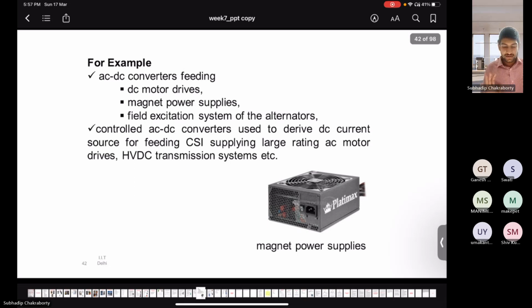My main point is this. I should understand my loads, the nature of my loads. Accordingly, I will select based on my cost and economic obligations. I will decide whether to go ahead with passive power filters and passive compensating elements, a low-cost arrangement for a more or less fixed kind of loading, or much more advanced compensating devices like the DStatCom. Even in remote areas with voltage-based power quality problems like fluctuations and notches, I will go ahead with much more sophisticated devices like the UPQC, which is capable of solving both voltage quality and current quality problems, such that my grid is not seeing those fluctuations or harmonic distortions.